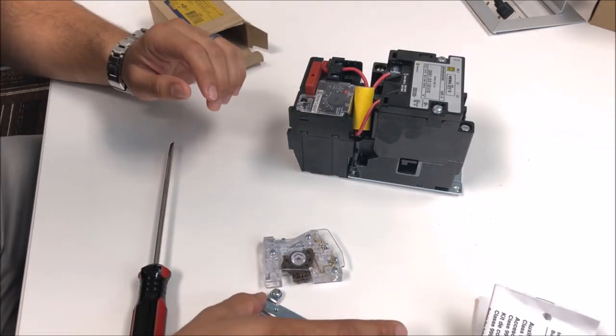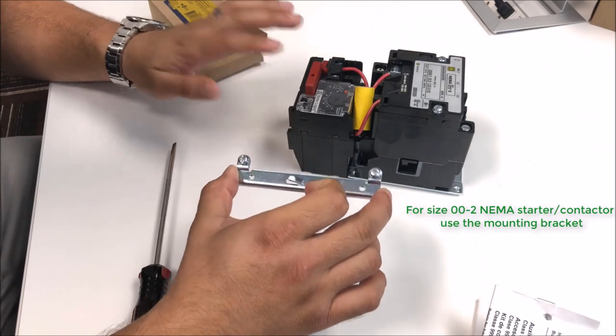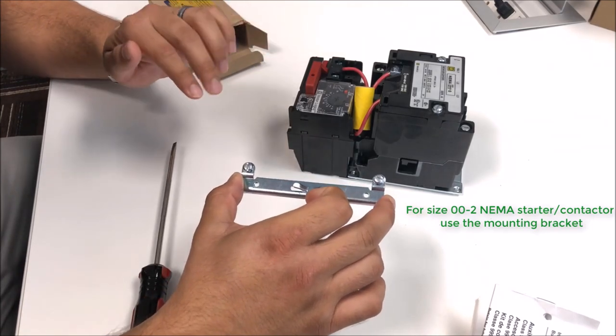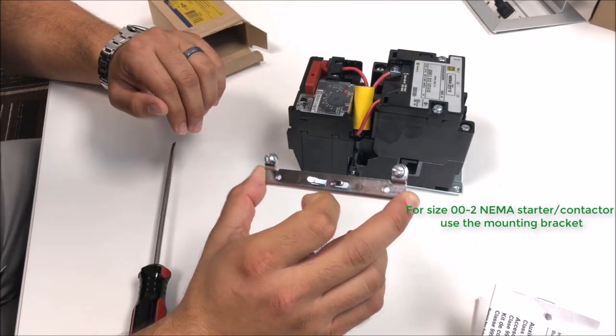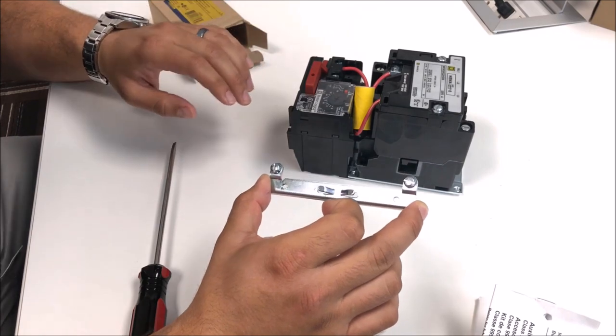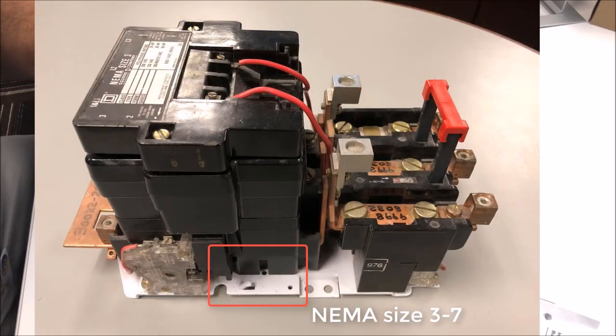To mount these using the mounting plate, for a size double aught to size two you'll use the mounting plate that comes with the prepackaged auxiliary kit. On a size three through seven, the mounting plate itself actually has them built into the device.